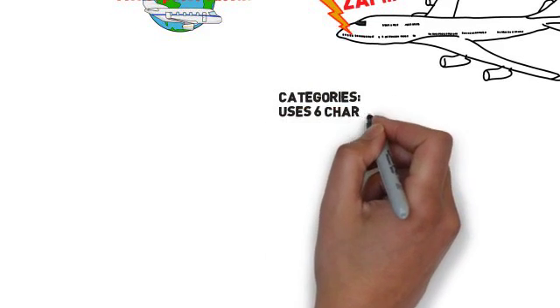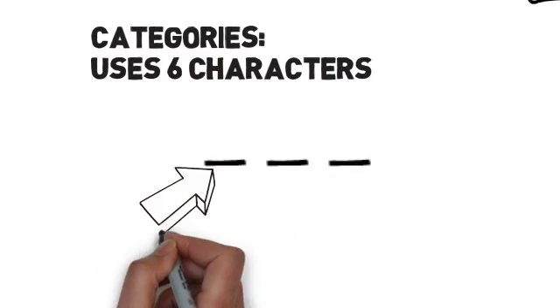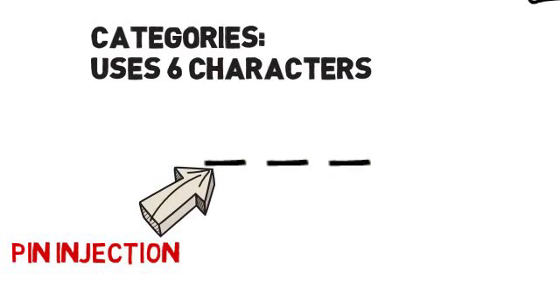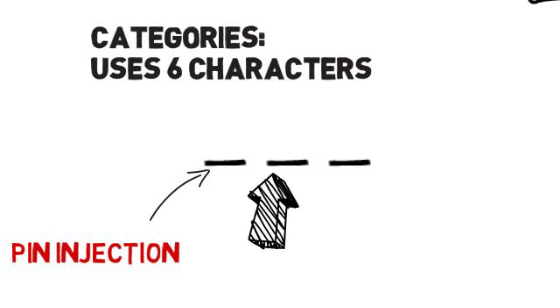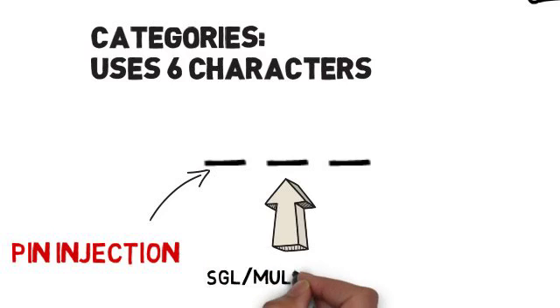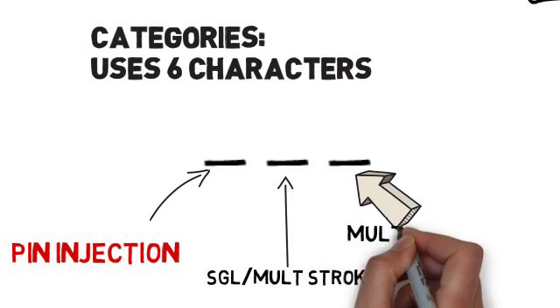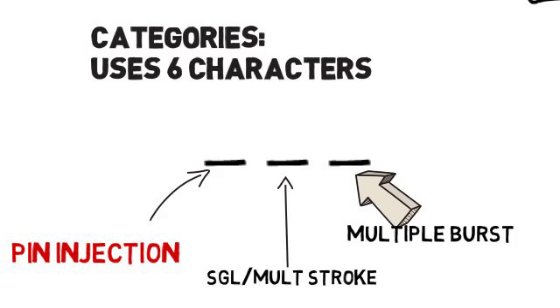Now the categories for section 22 consist of six characters. The first two call out the pin injection waveform set and test levels. The second set, or the third and fourth characters, refer to the single and multiple stroke waveform set and level. And finally, the last two characters determine the multiple burst waveform set and multiple burst level.